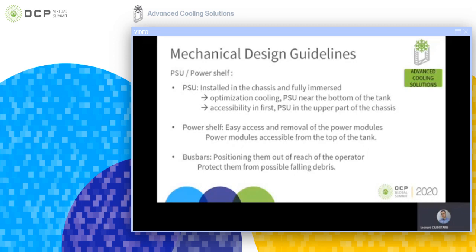PSU or power shelf. According to the tank configuration, both PSU and power shelf can be used. Each of these options has its benefits and drawbacks. PSU modules can be fully submerged, either near the bottom of the tank for optimized cooling or at the liquid level for ease of access. We recommend removing, disconnecting, or shutting down via software the PSU fan.